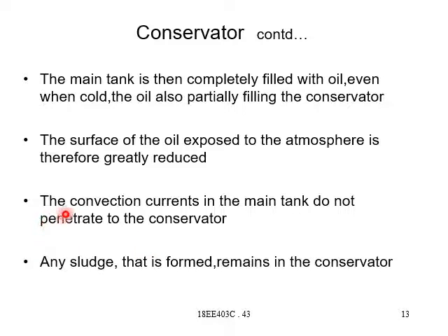So thereby the convection currents in the main tank do not penetrate into the conservator. And any sludge that is formed will remain in the conservator tank only, that may not enter into the transformer's tank, where actually the process is going on, like step down or step up of the voltages.